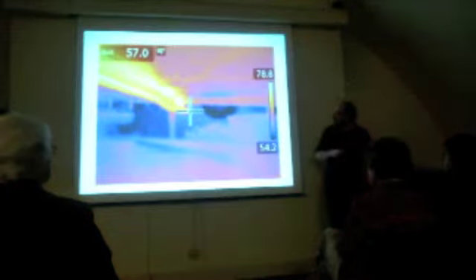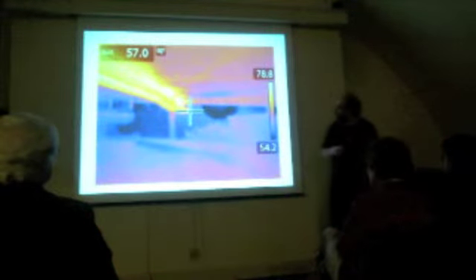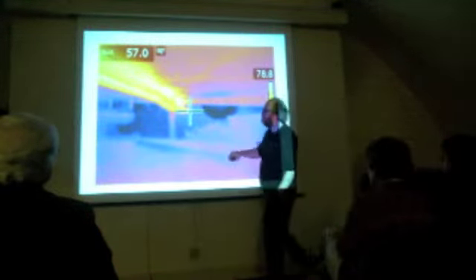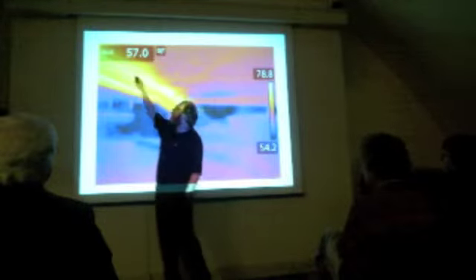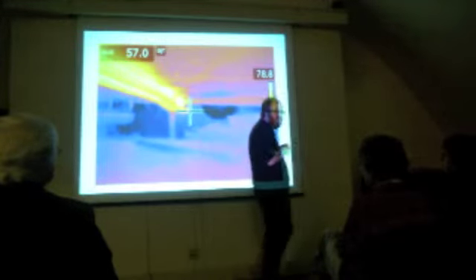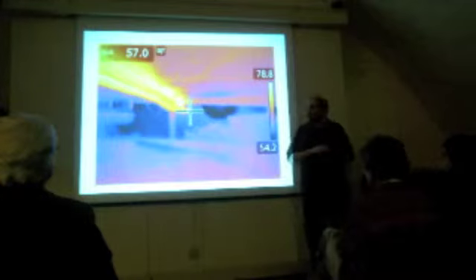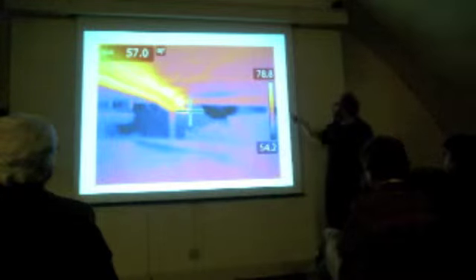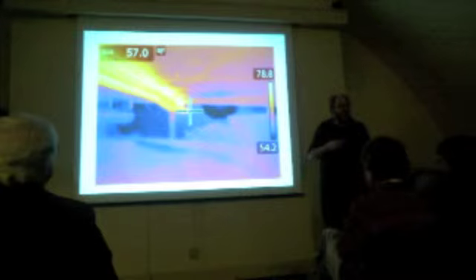So those kinds of pieces are driving a little bit of it. There are other things. This is in your crawl space. This is some of the piping for the hot water system. Those pipes are relatively uninsulated in there, so you can see they're 80-degree pipes in 50-degree air, so you're losing some of that energy into the cold air.